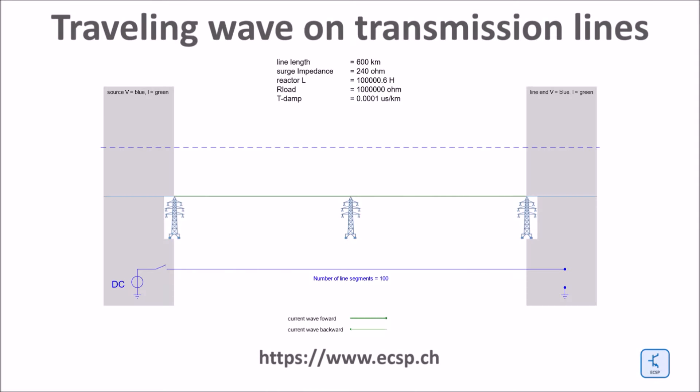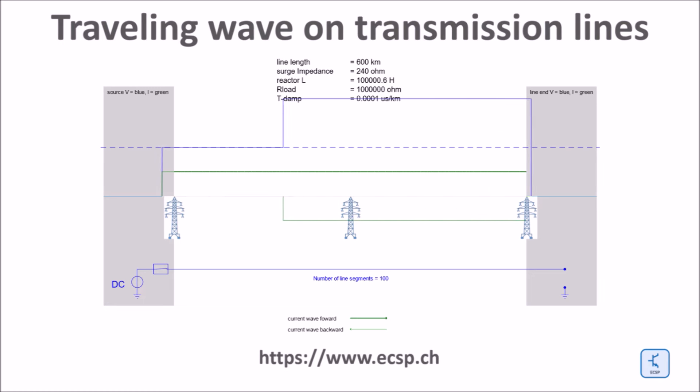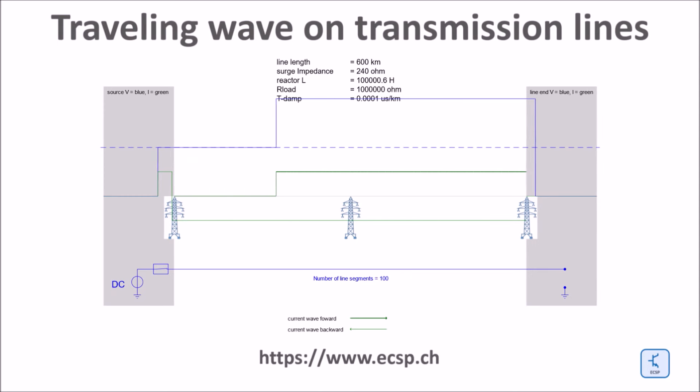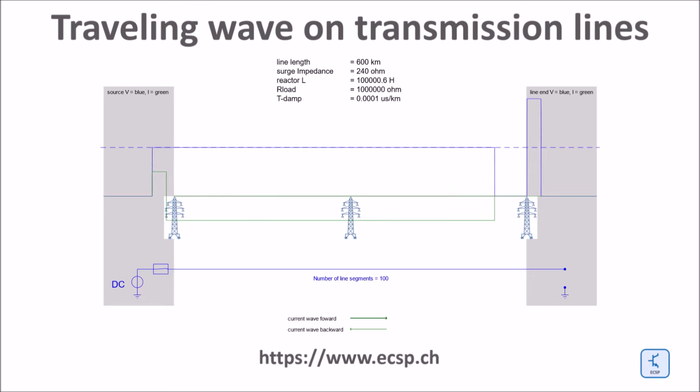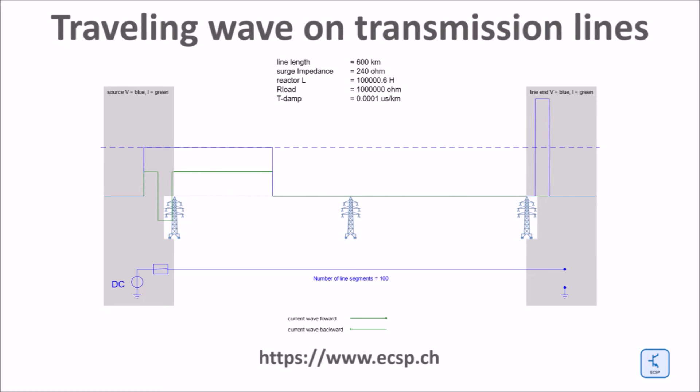Here is a traveling wave on an open-end 600 kilometer long overhead line. The dark green slightly bold curve traveling on the line in forward direction as well as the blue voltage surge traveling on the line have been initiated by closing the breaker on the left end of the line. The closing operation of the breaker connects a DC source to the line. The relation between the voltage surge and the current surge is given by the surge impedance of the line.